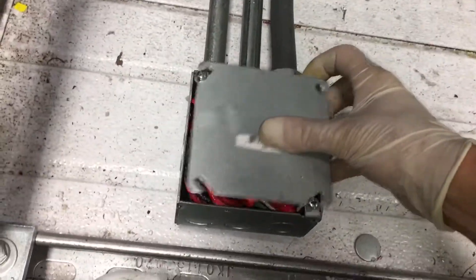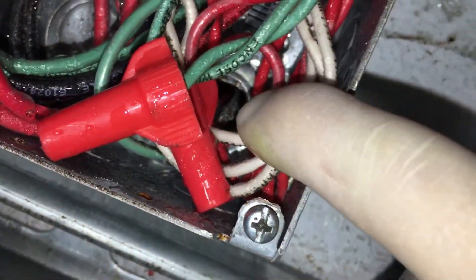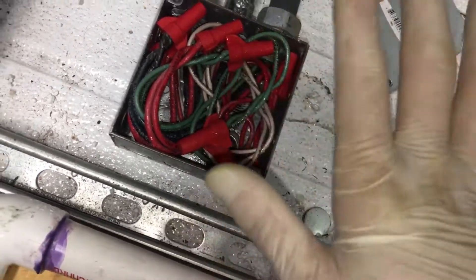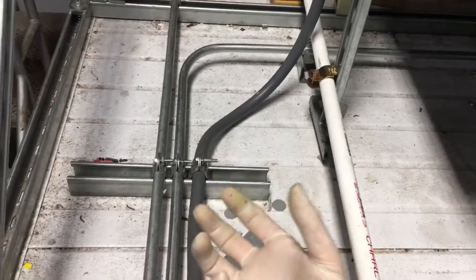When you look in here, what do you see? Lots and lots of condensation. Right there is the access hole going down into the room — positive pressure, 70–80 percent humidity coming up into the atmosphere out here. It's a lower pressure, and it hits the metal box. It also travels up the conduit and goes inside. Some of this conduit is going on a downward slope — if I were to cut the conduit over there and pick it up, a ton of water would come out. The conduit literally fills up totally with water.